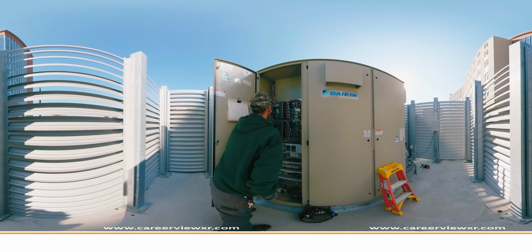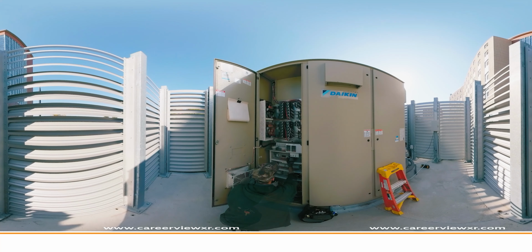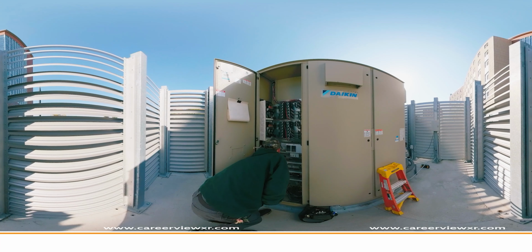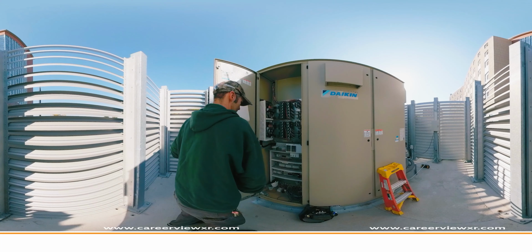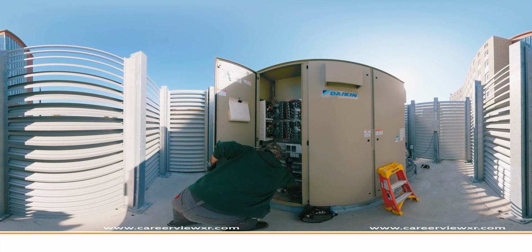This chiller is shut down due to a low flow alarm. The chiller's flow switch automatically shuts the chiller down when it stopped detecting proper flow. Andy checks the field controls. He tightens up a wire connection and operation resumes.